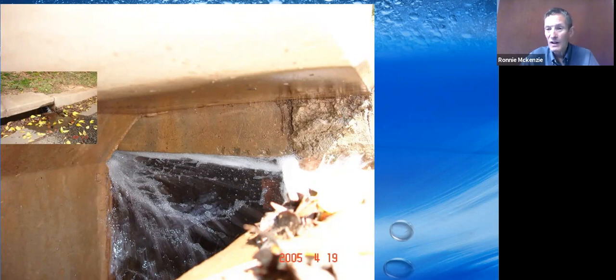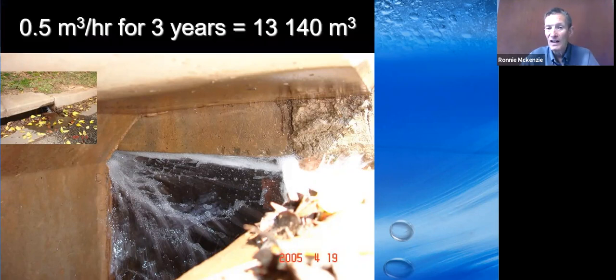As a result, this leak ran for over 3 years, and it ran up a total loss of 13,000 cubes. So the message here is, it's not always the size of the leak that will dictate how much water you lose. It's how long you take to fix it. And it's very important to fix even small leaks, especially if they've been reported.